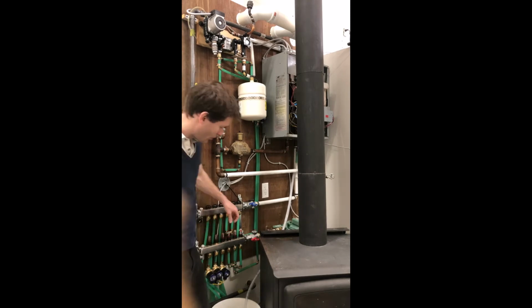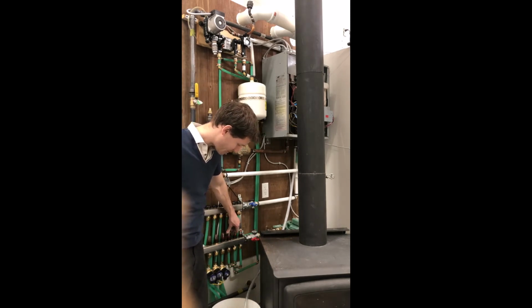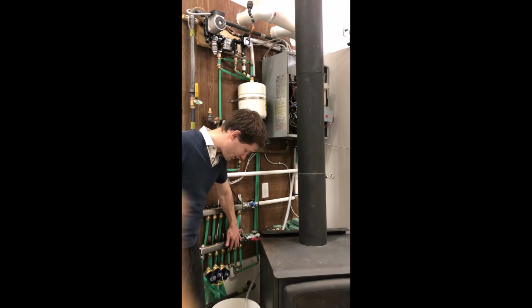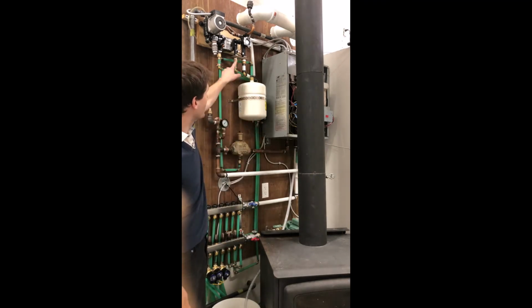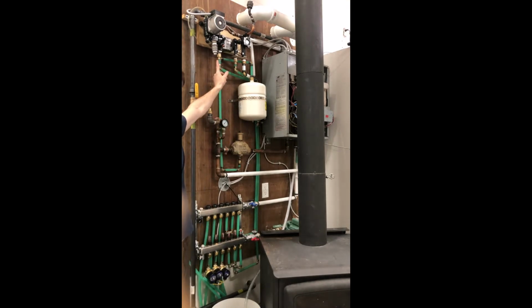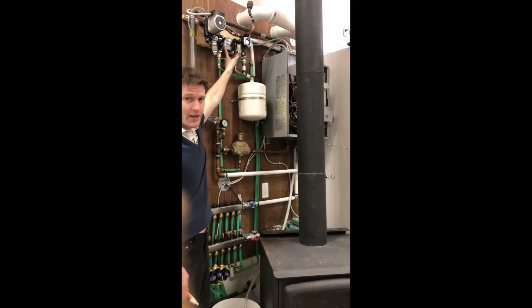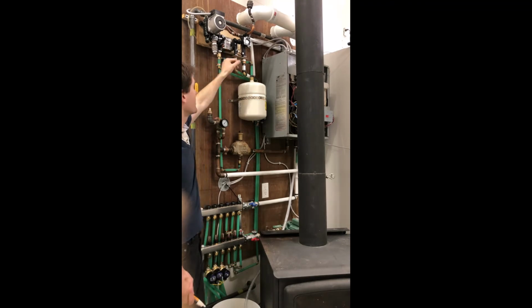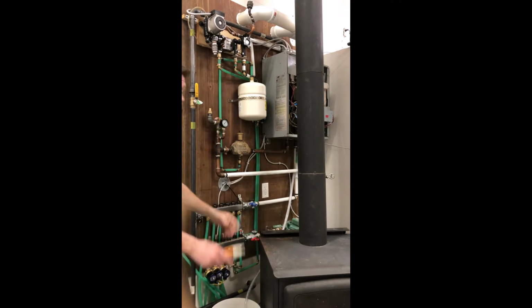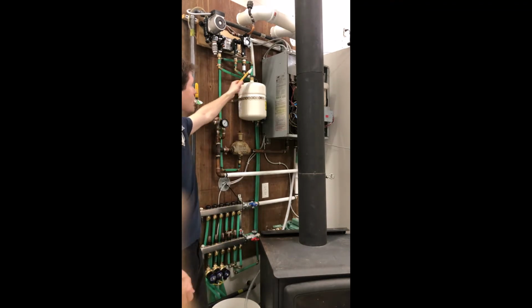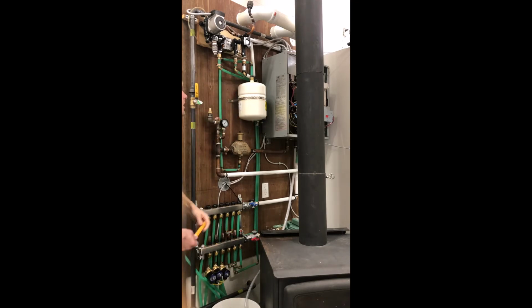Right now, what I've got going on here is 2 of these loops merge into one, then come up here and go into our water-to-water heat exchanger for the hot tub. This is your plate heat exchanger — a 14 plate heat exchanger — and I've got a Grundfos pump up here, a nice quiet efficient pump. My hot tub loop on the isolated hot tub side is 3/4 inch PEX, and the hot water coming up to the heat exchanger is 1/2 inch PEX, and that's a little bit of a problem.